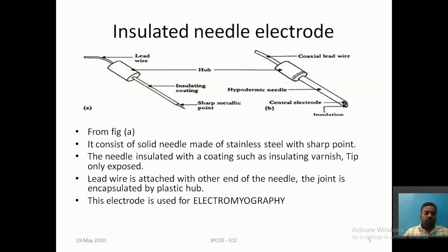Then a lead wire is attached. Lead wire means the probe. In our CRO we are using a probe, right? That is a lead wire. So that lead wire is attached to the other end of the needle, joined to the encapsulated plastic hub. This is an encapsulated plastic hub, and this is a lead wire. This lead wire is connected with the EMG recorder. So this is our complete setup: the lead wire, the plastic hub, and then the plastic hub is connected with our insulated needle electrode.